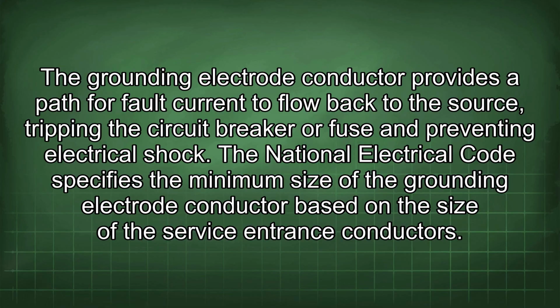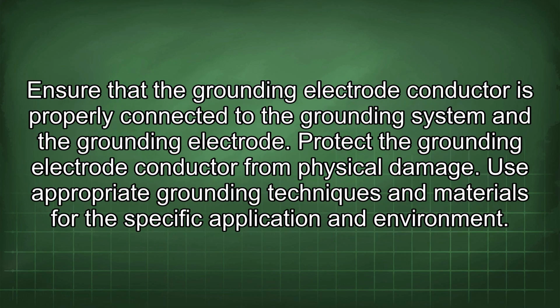The National Electrical Code specifies the minimum size of the grounding electrode conductor based on the size of the service entrance conductors. Ensure that the grounding electrode conductor is properly connected to the grounding system and the grounding electrode. Protect the grounding electrode conductor from physical damage. Use appropriate grounding techniques and materials for the specific application and environment.